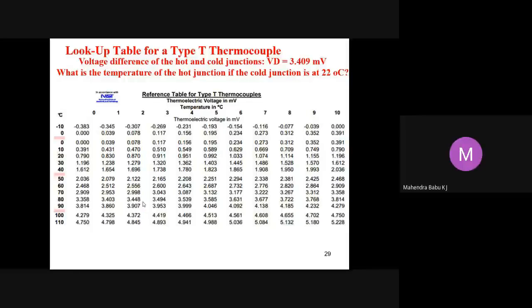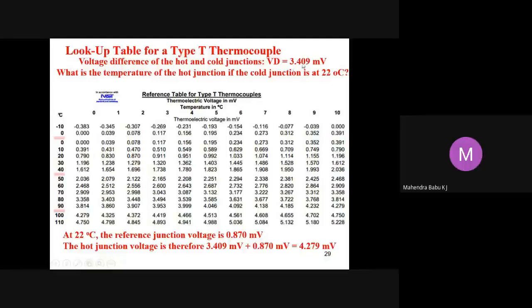How to do this? At 22 degrees Celsius, that is the reference junction, we have 20 here, and you move to the right side to the column under 2. That gives the voltage at 22 degrees Celsius, which is equal to 0.870. So that is the reference junction voltage at 22 degrees Celsius. Now the voltage difference is 3.409 millivolts, therefore the hot junction voltage is 3.409 millivolts plus 0.870 millivolts, which is equal to 4.279 millivolts.